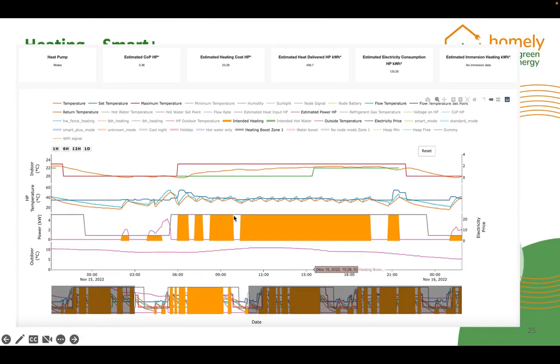I've added in a snapshot of the dashboard just so that we can show the behavior of this in Smart Plus mode, which is our tariff optimization service, but also to show you how Homely actually does what we were just talking about before. So if you look at the graph here, these are the set points of the customer: 20 degrees throughout the day and 22 degrees in the evening. For this customer, the internal temperature has been slowly rising towards that evening set point, and as you can see here, the flow temperatures have been slowly decreasing throughout the day so that the house gets warmed up slowly. Even at 10 degrees outside, the heat pump was running at nearly 35 flow temperature, just trying to maintain that 22 degrees indoors.